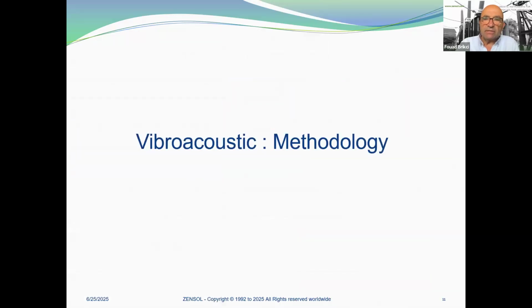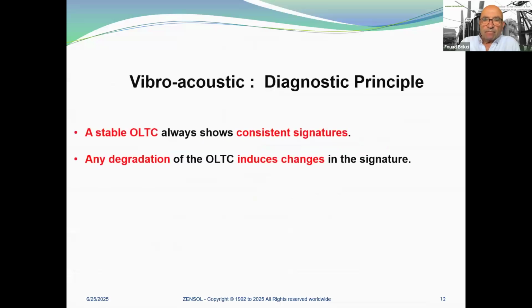So what is the vibroacoustic methodology? Each operation of any on-load tap changer produces a specific vibroacoustic wave pattern, or what we call a signature or a fingerprint. With a vibroacoustic sensor, which is an accelerometer, we can record the signal exactly the same way a stethoscope picks up a person's heartbeat. What is important is that a stable OLTC always shows consistent signatures. Any degradation of the OLTC induces changes in the signature. So this is the principle of the vibroacoustic. We always have a reference which we can compare.